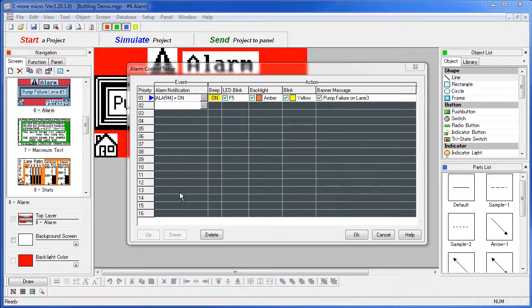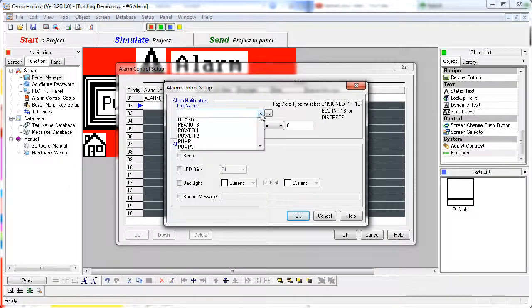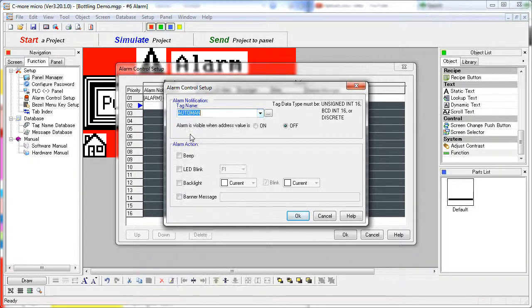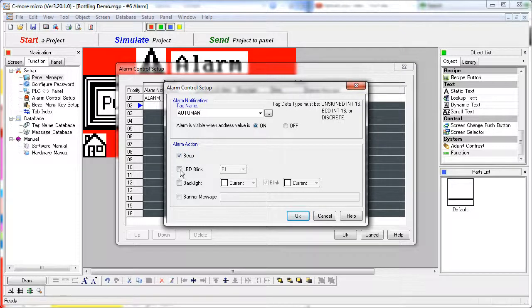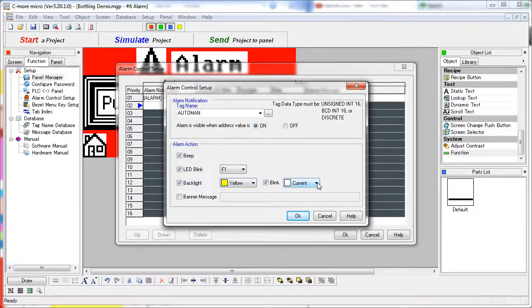In this dialog we can create up to 16 different alarm conditions. We just select the tag to generate the alarms — we'll grab one out of our database here — then select the state that generates the alarm, on or off for a discrete tag, and then enable the options you want. You can turn on the beeps, have the LED blink on any function key you want, have the backlight turn on to any color you want or blink between that color and another color. You can even have a banner message appear at the top.